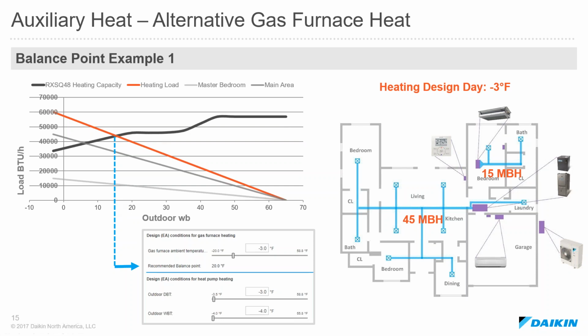So the balance point is provided in increments of 5. So it's falling on 16 degrees, so it's going to round that up to 20 degrees. And it's obviously always going to round up. You never want to actually round down. So in this case, 20 degrees is when you would switch over based off of that 60 MBH load occurring at -3 degrees outside.